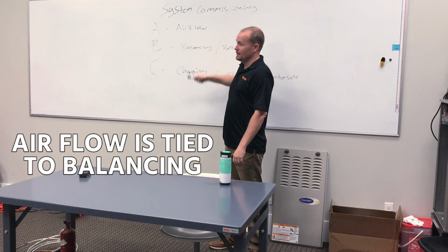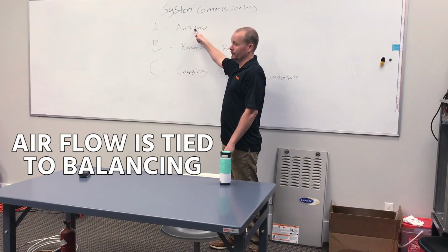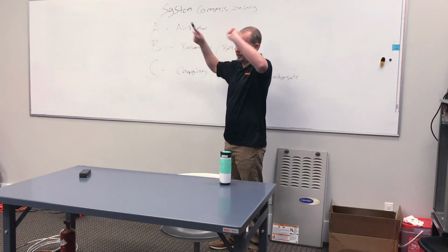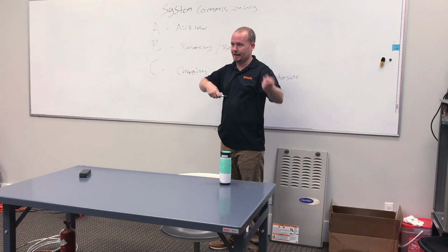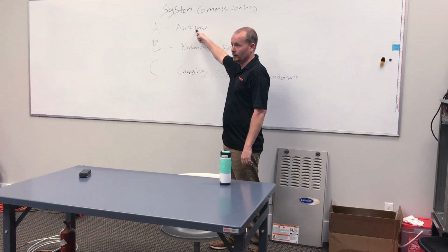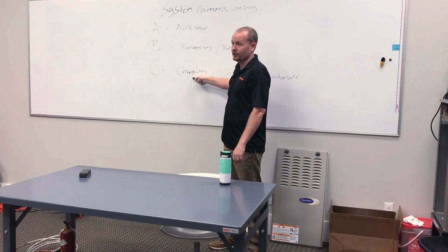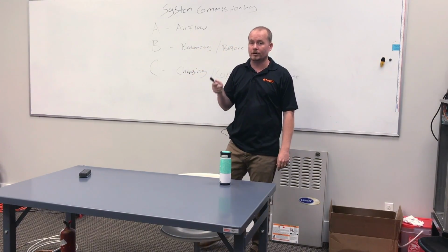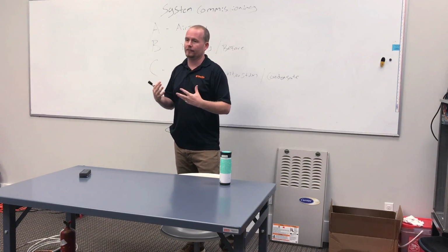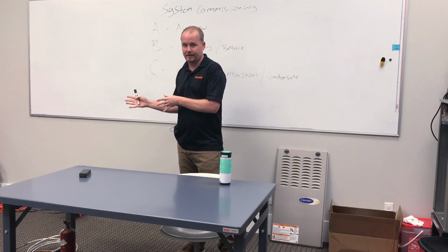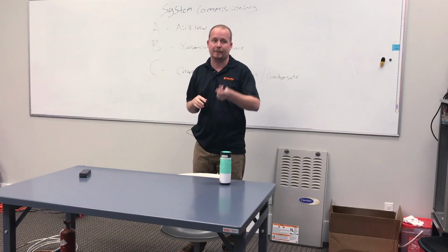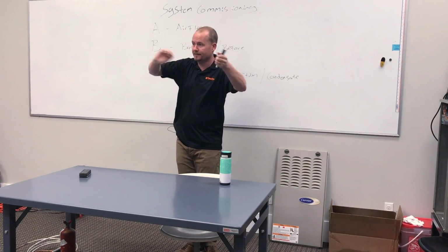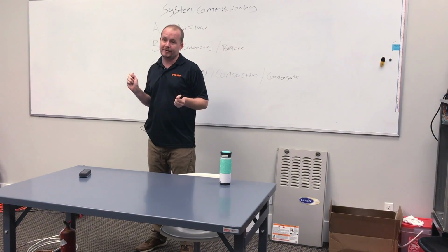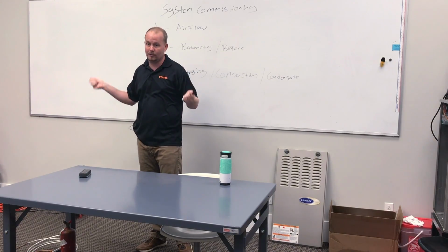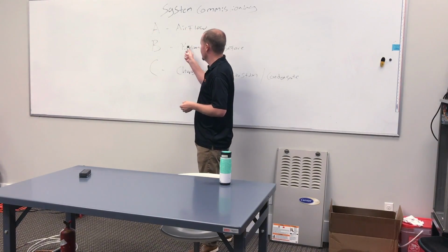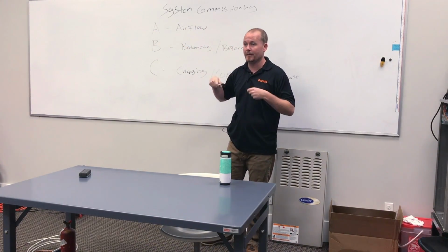Airflow is also tied to balancing. If you set up a system airflow, and then afterwards you go in and you make all kinds of changes to it, you damper this down, damper that down, whatever, it can change system airflow, which can then affect your charging. So I don't want you separating out airflow and balancing from that commissioning because it's going to have effects. If you check a 0.5 static and then you go in and close down a bunch of dampers, well, now your static could be 0.6 or 0.65 or whatever. And so you have to make the balancing part of this airflow test when we're making ductwork changes.